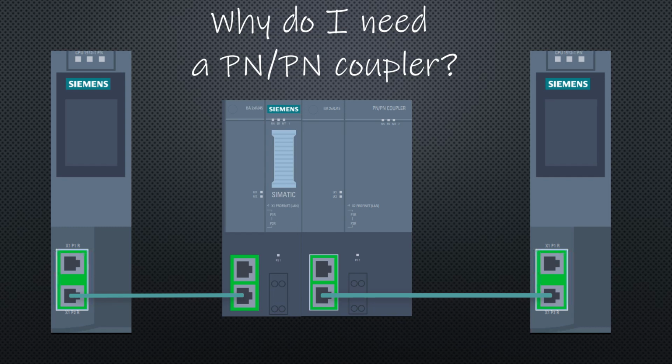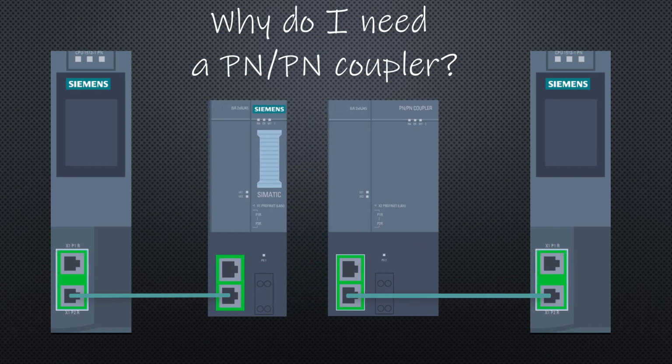How does it work? Each coupler has two sides. Each side is a device of its own with a transfer area. The I/O controllers on each side of the coupler talk to the respective transfer areas, and the coupler copies the data across.